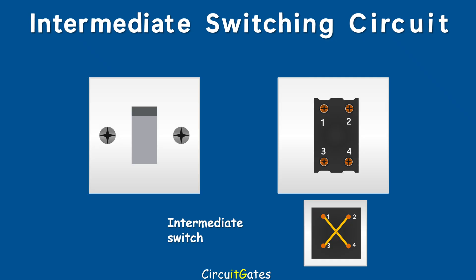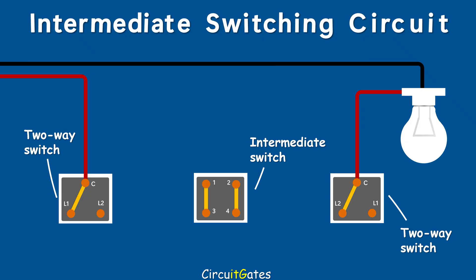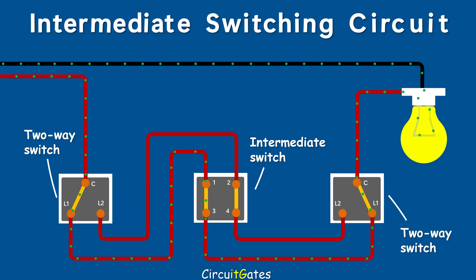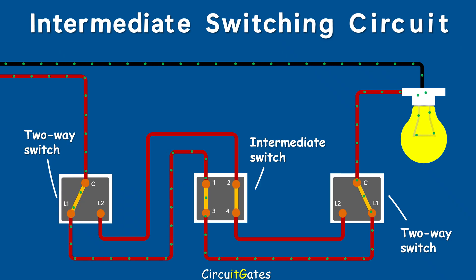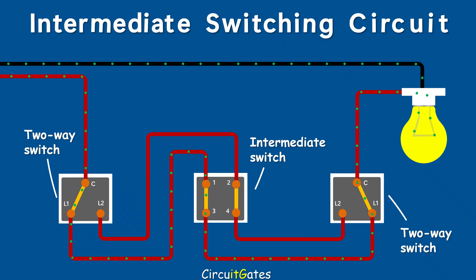To wire an intermediate switching circuit, we simply add an intermediate switch between the two two-way switches. Connect the terminals labeled L1 of the two-way switches to the terminals labeled 1 and 3 of the intermediate switch, and the terminals labeled L2 of the two-way switches to terminals labeled 2 and 4 of the intermediate switch. In an intermediate switching circuit, for the lamp to be illuminated, one path must be complete — starting from the common terminal of the first switch, going through the intermediate switch, up to the common terminal of the other two-way switch. If there is not a complete path, the lamp will not be illuminated.